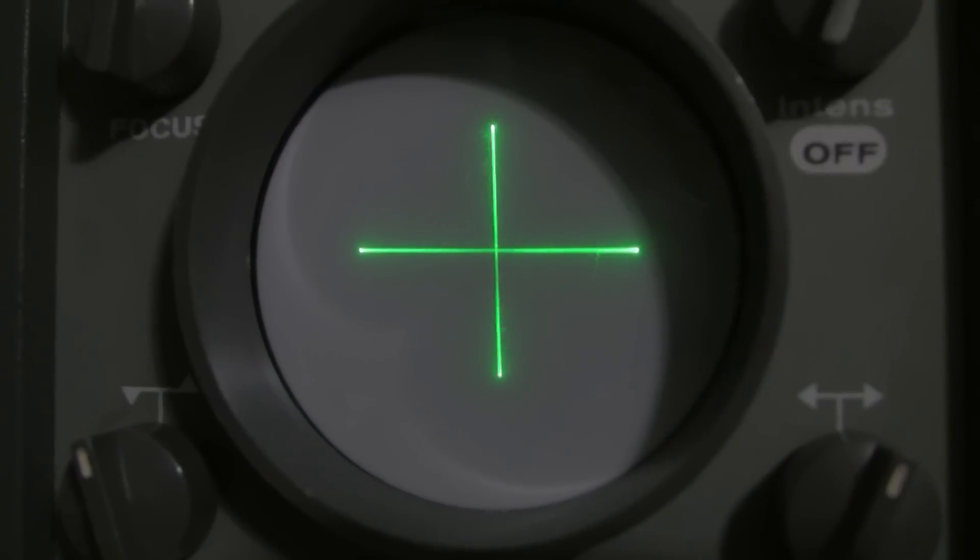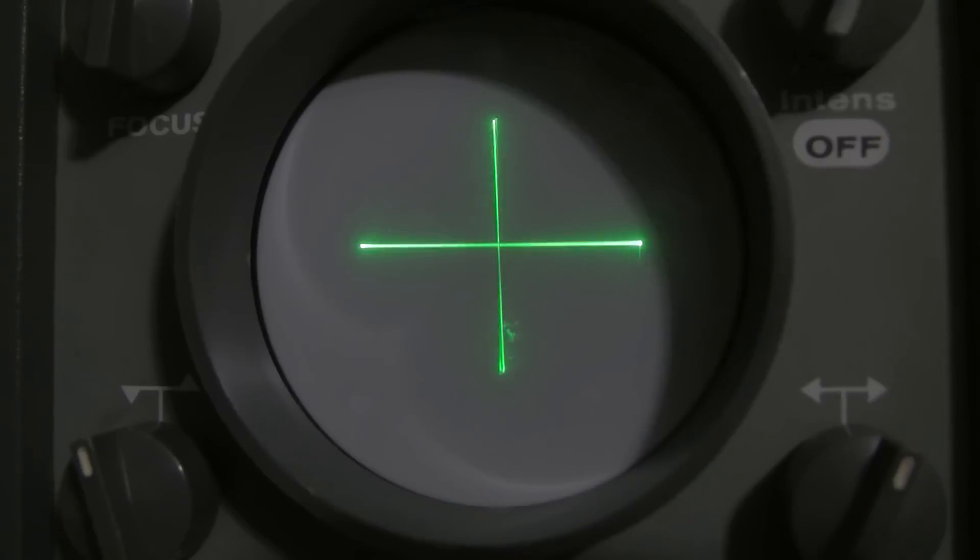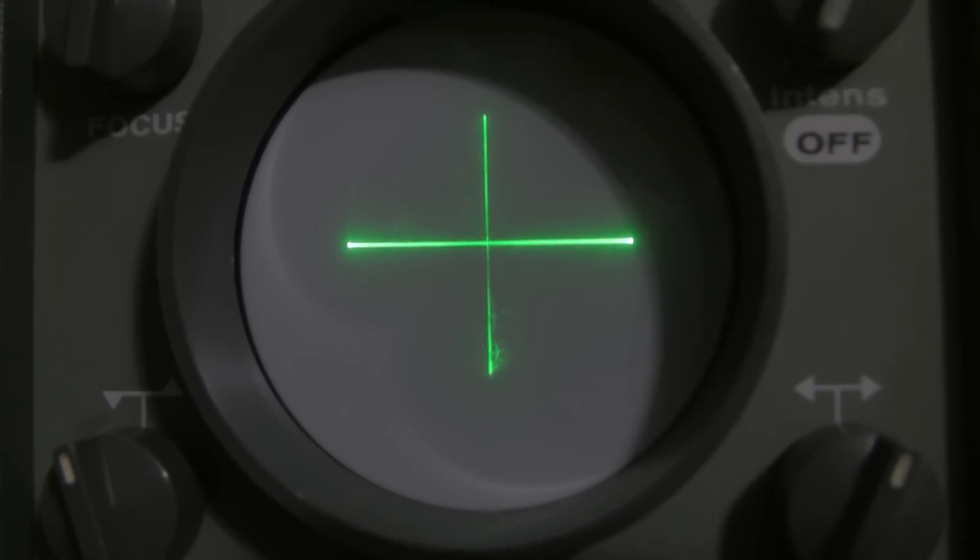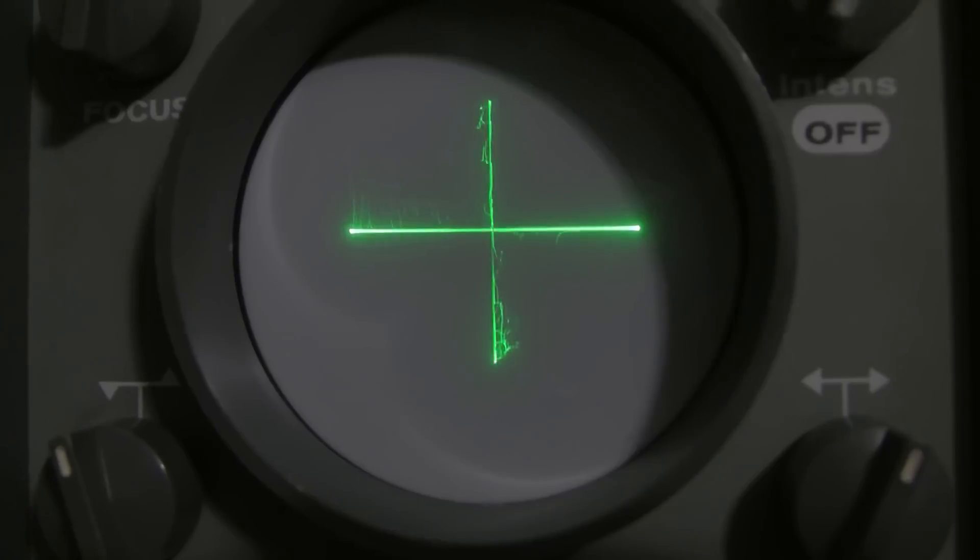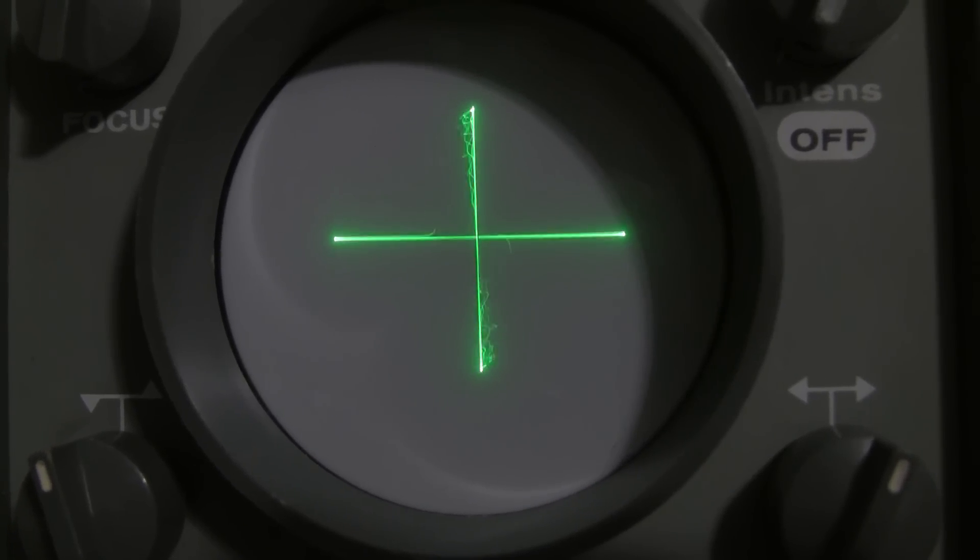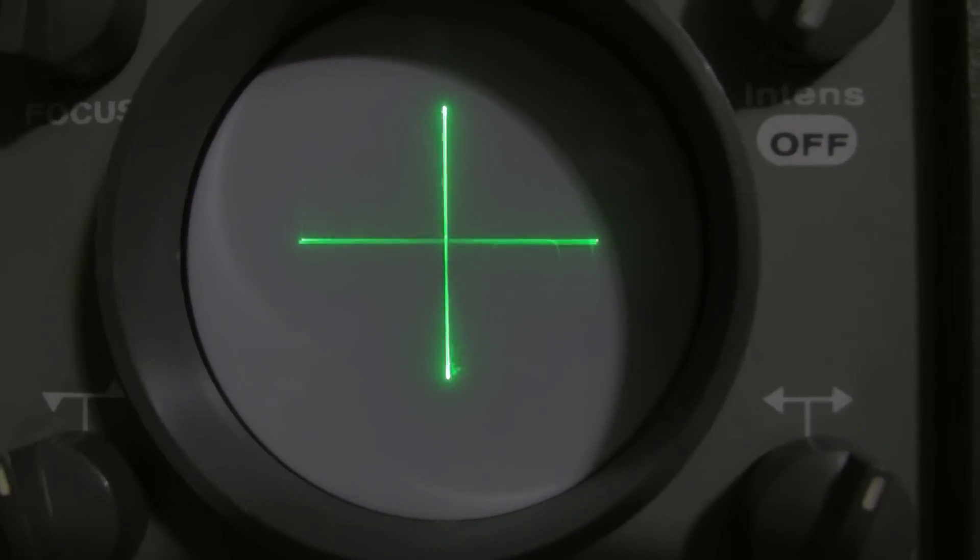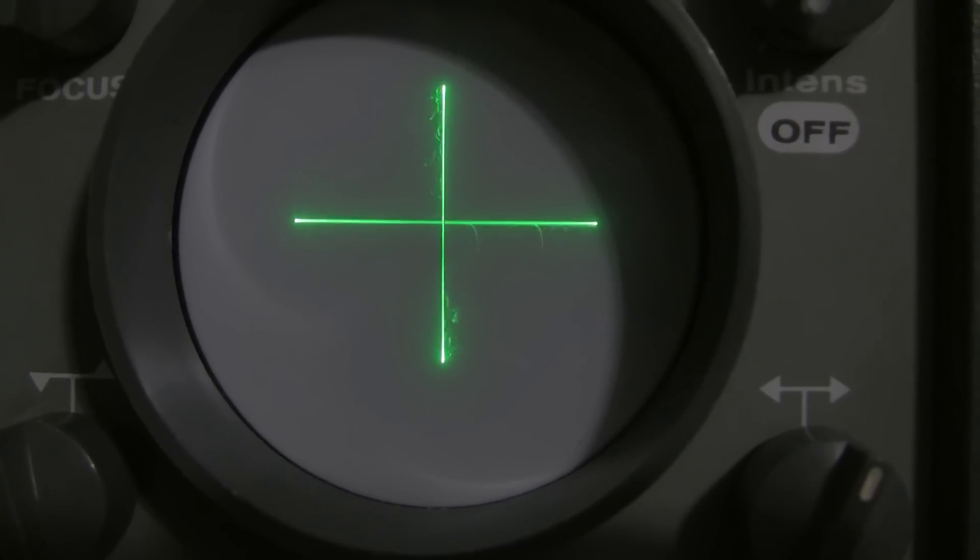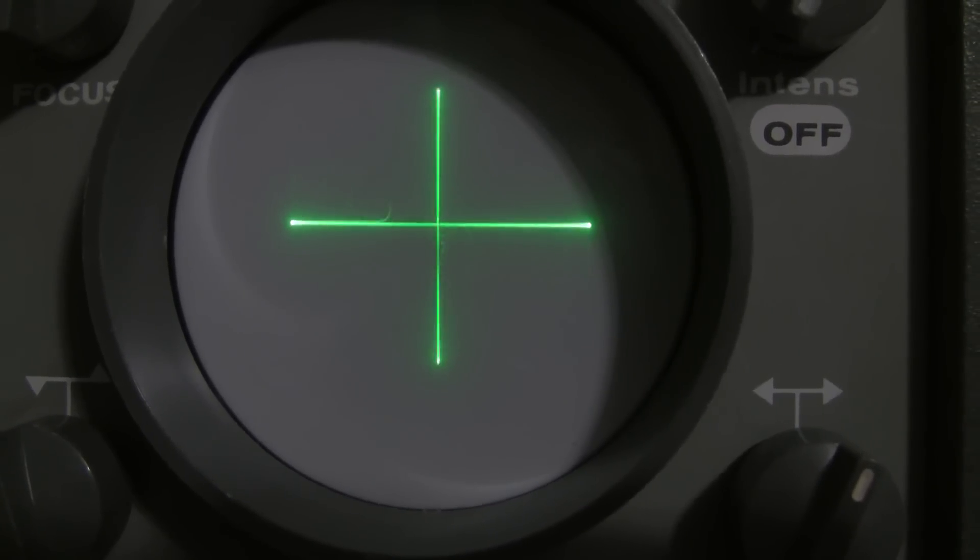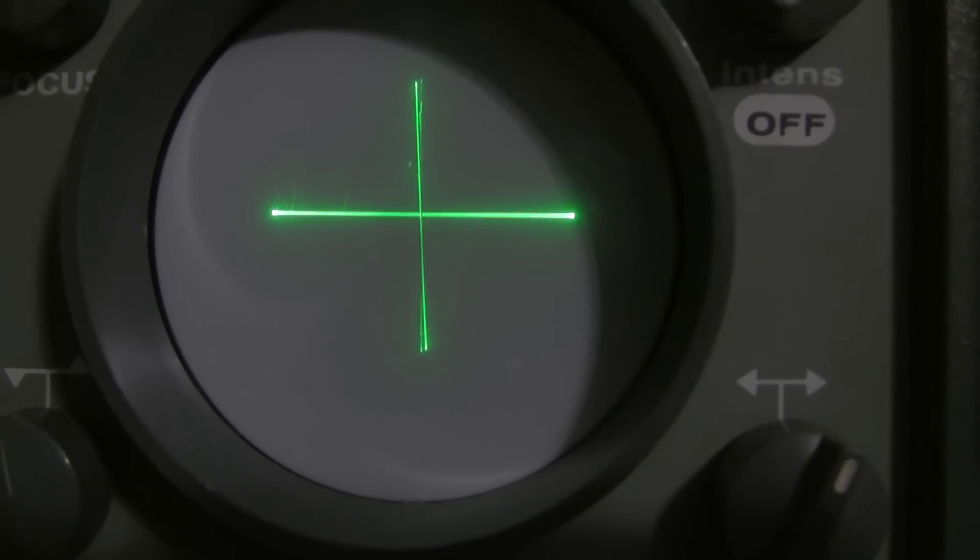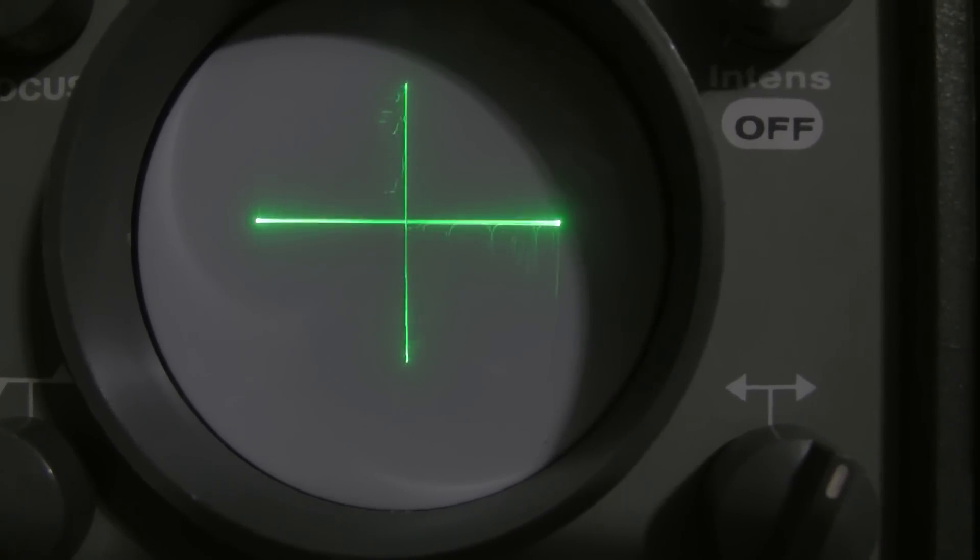Here we have a relay that's got a lot of contact resistance and it even looks like the mechanism inside of the relay itself is sticky. So you can see that by the movement on this axis here twisting. You can tell that there's quite a bit of contact resistance in there. And it looks like there is some delay in the switching.